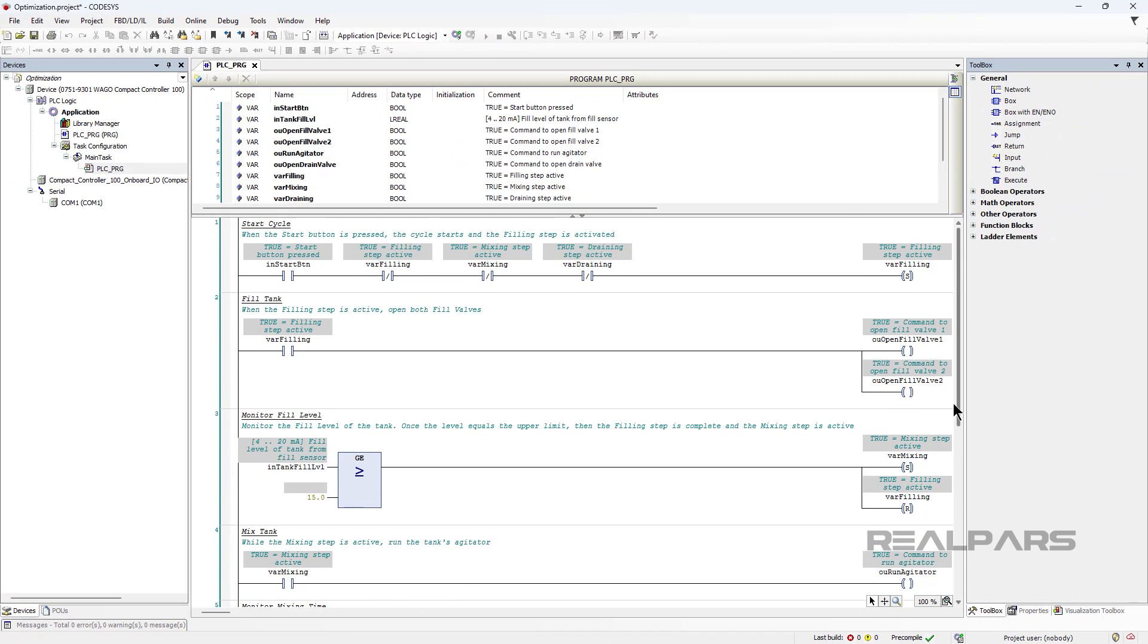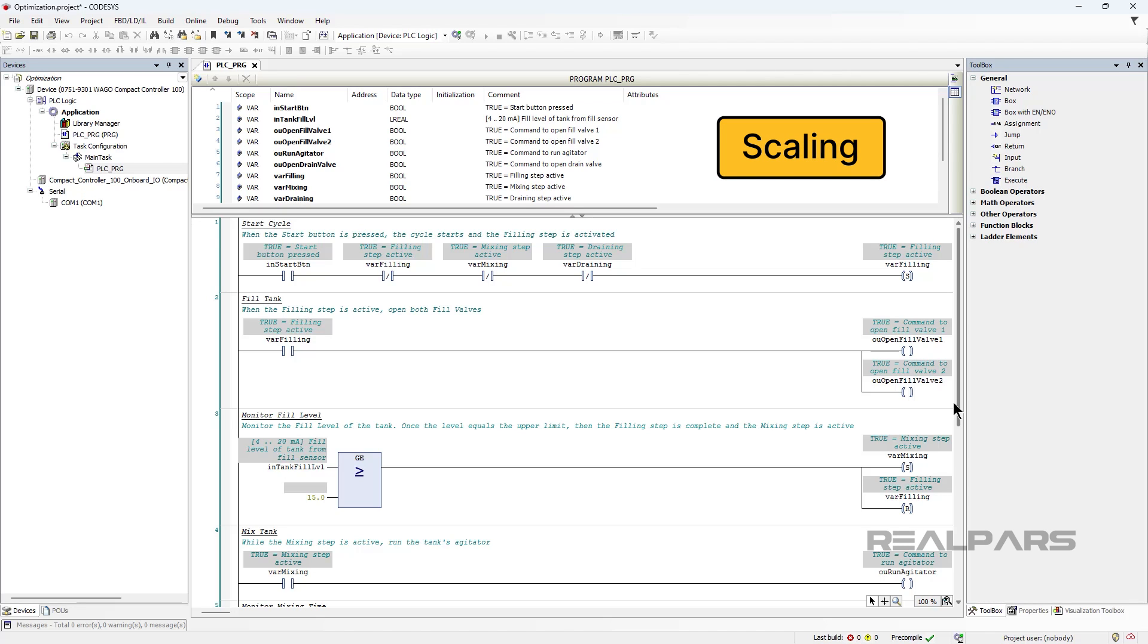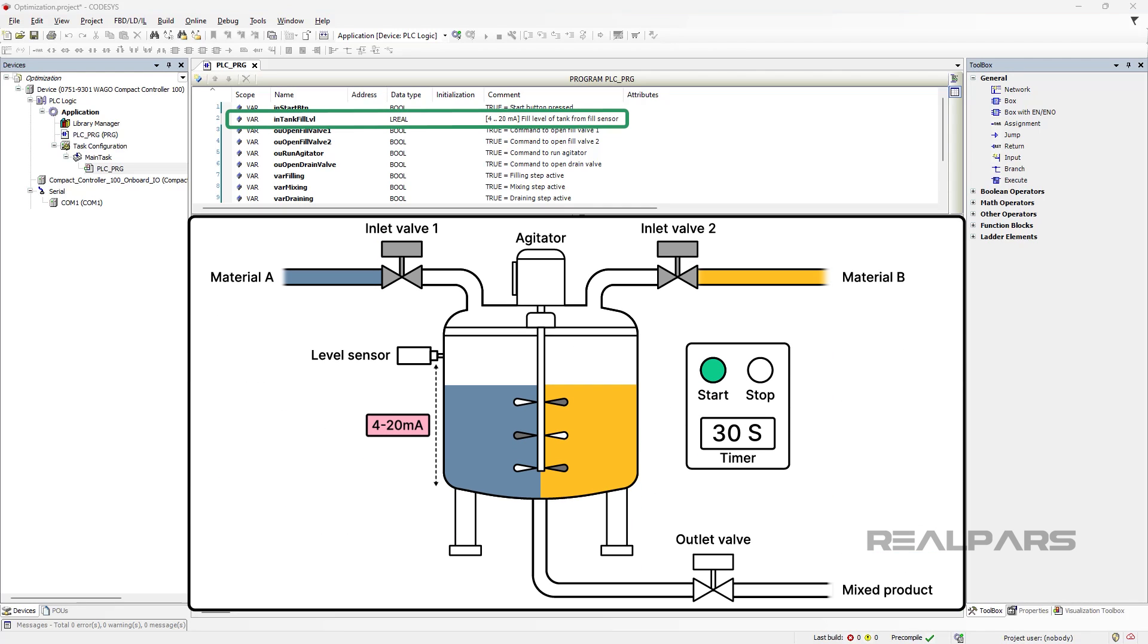As well as adding comments to our code, we can make our code easier to understand by scaling raw data to use engineering values and avoiding the use of hard-coded constants. At the moment, the tank level is expressed in a value between 4 and 20 milliamps, but what does that actually mean? How much liquid is in the tank when the sensor reads a value like 10 milliamps? How much liquid has to be in the tank for it to be considered full?